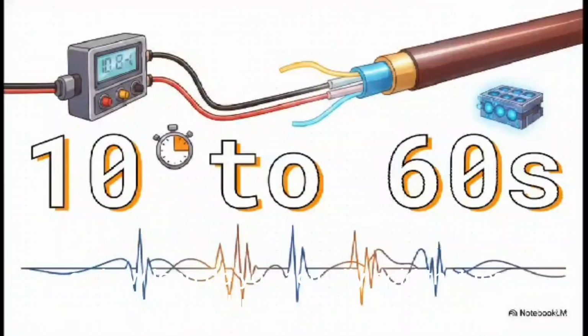So how long do you actually hold that test button down for? 10 to 60. You generally need to hold the button for 10 to 60 seconds, especially on highly capacitive devices or really long cable runs. It simply takes time for the instrument to apply the high DC voltage properly and for the resistance reading on the screen to finally stabilize. So just be patient. Let the meter do its work so you get a truly accurate reading.